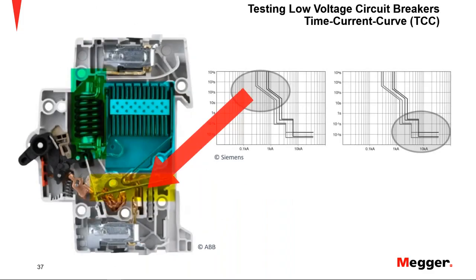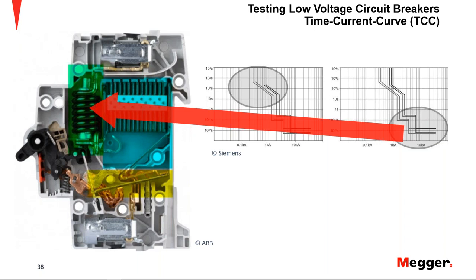So when we're testing the overload section, when we test the overload elements of the circuit breaker, in reality, physically, we're testing the thermal protection of my circuit breaker, highlighted here in yellow. And when we look at the instantaneous part of the curve, we're going to measure the performance of the magnetic protection of my circuit breaker. We typically call these circuit breakers thermomagnetic. So again, those two sections are described in the time current curve that we just discussed. So let's go into the testing itself.